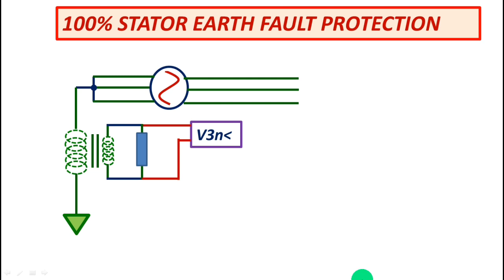Now third harmonic voltage measured at the neutral of the generator will drop for fault close to neutral.